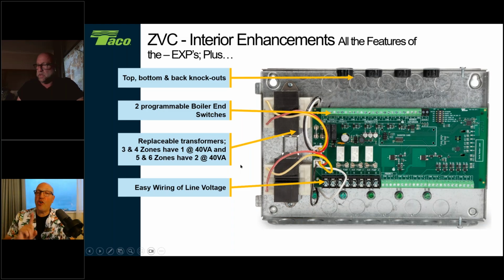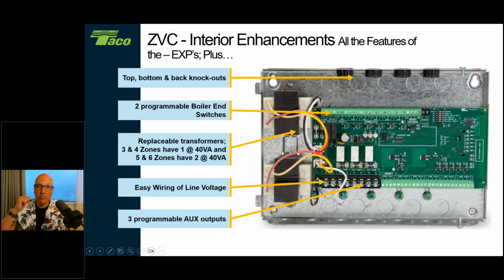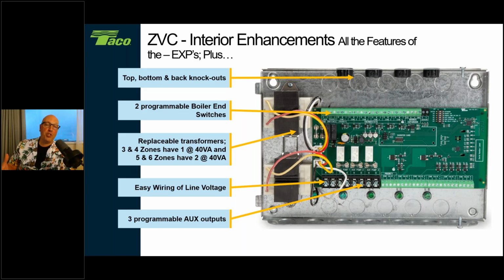We have also added a terminal now for your line voltage coming into a zone valve board. Before, you had your black and white wires coming off the transformers loose, and you had to bring the power in and wire nut it together. We added a terminal. That was a big deal because we have also now made our pump switches line voltage as well. Our old pump switches were dry contacts. You had to bring line voltage in, just like you had to bring the line voltage into the transformers. Now that we landed it here on the board itself, we're making wiring all that much easier. So for those of you that may be replacing, say, a ZVC on an existing project, just make sure that you follow the wiring, because these are already hot terminals.